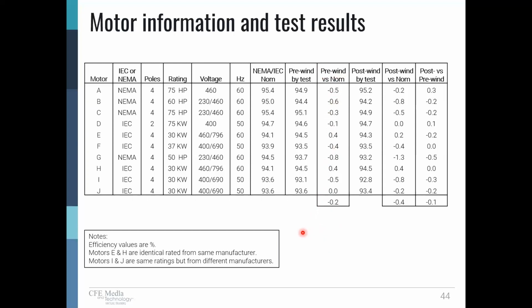And if you want to do some deeper diving, motors E and H are the same rating from the same manufacturer. They're identical. Motors I and J happen to be the same rating, but they're from 2 different manufacturers. So you can see pre-rewind by test, 93.1, 93.6. If you knew that from the nameplate, and I wanted to buy a motor and make sure I'm going to get my big payback, I'd be picking the one at 93.6.